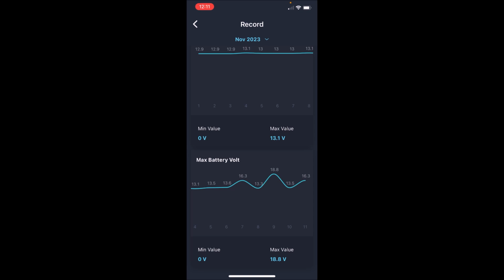So what happens when you see these spikes is one or more of the batteries are slightly out of balance. That means one cell is much higher than the rest, or most likely one cell is much lower than the rest. So as it's charging up and charging up in the bank, it gets to a point where one of the cells exceeds 3.65 volts. And the BMS will record a cell over voltage error and shut off the BMS and shut down the battery, because they don't want to overcharge that single cell. So what happens when the BMS cuts off, you get this voltage spike. It records like a voltage spike when it cuts off. So that's what we're doing.